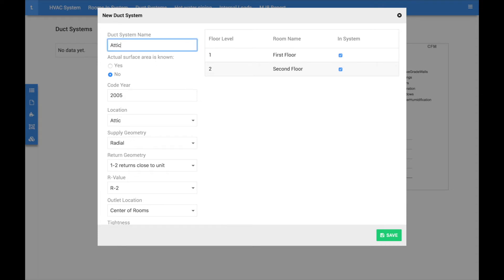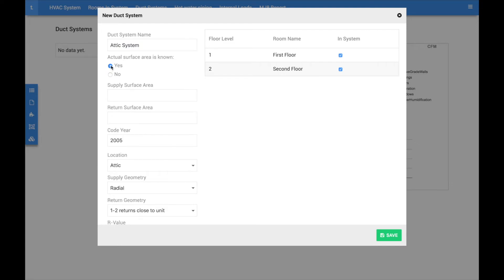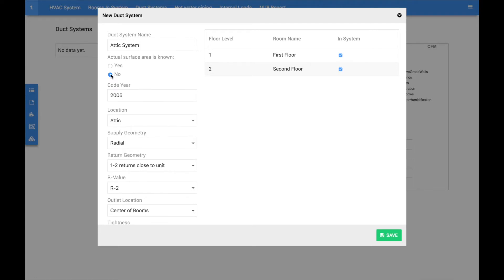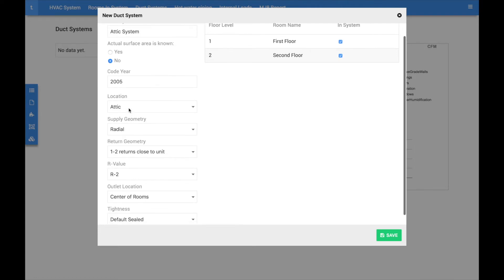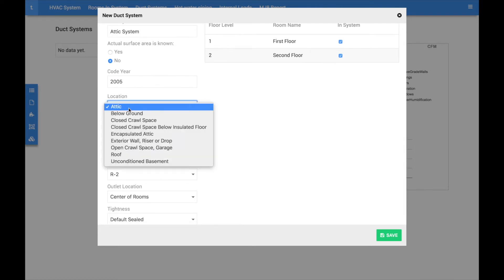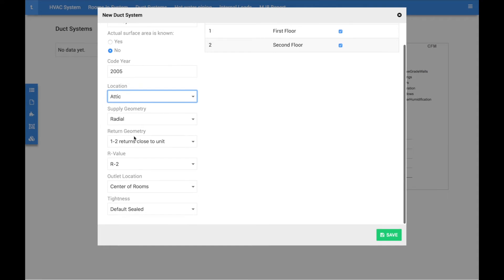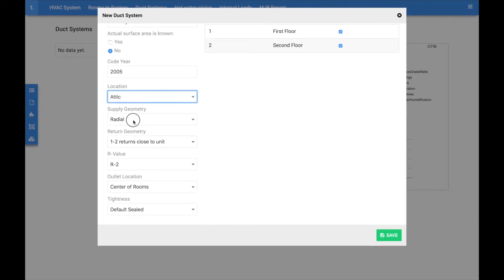If actual surface area of the ductwork is known, select yes and enter the values. Otherwise, CoolCalc will automatically calculate the amount of ductwork based on the square footage of the room served and where the ductwork is located.